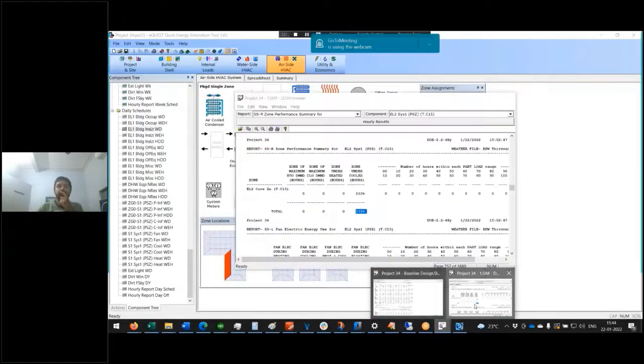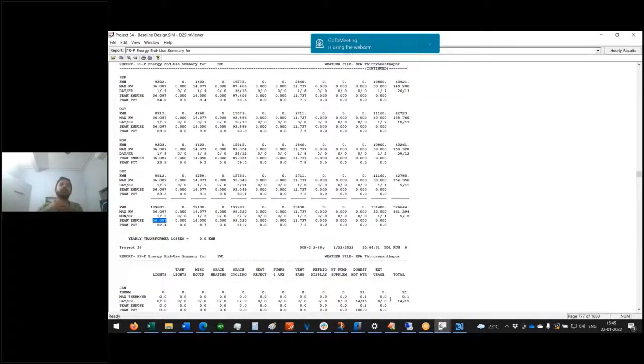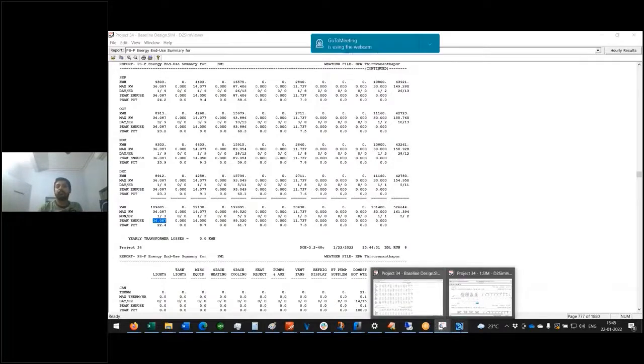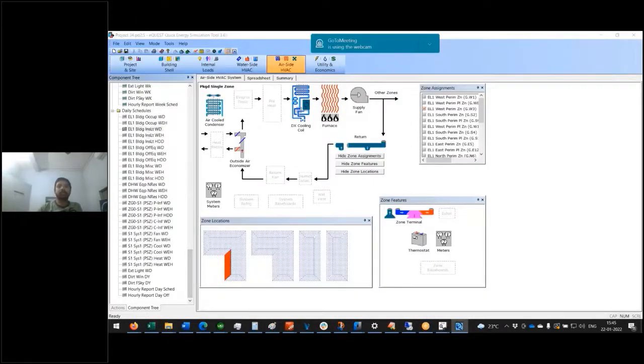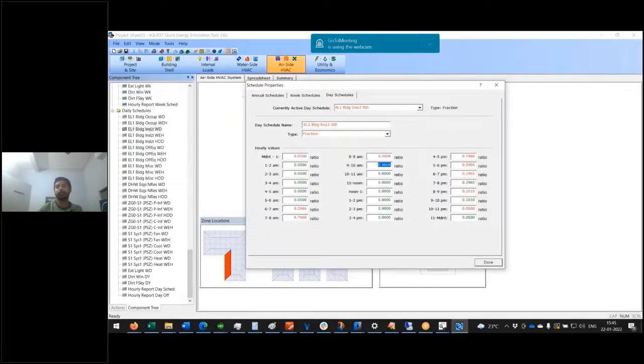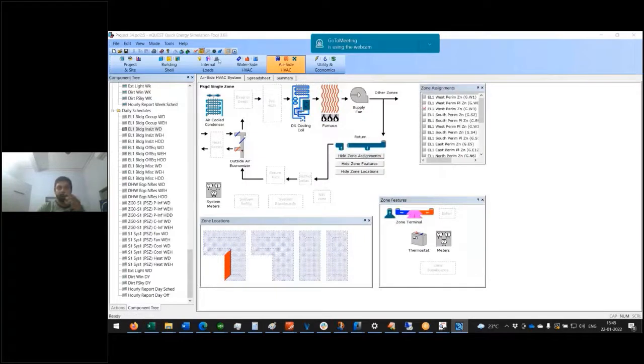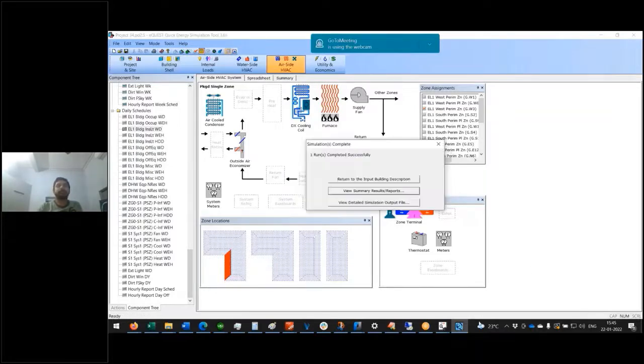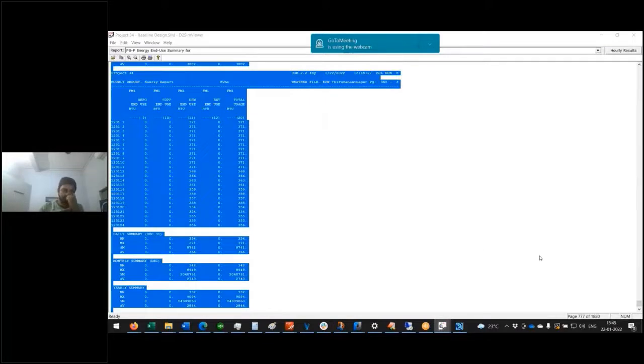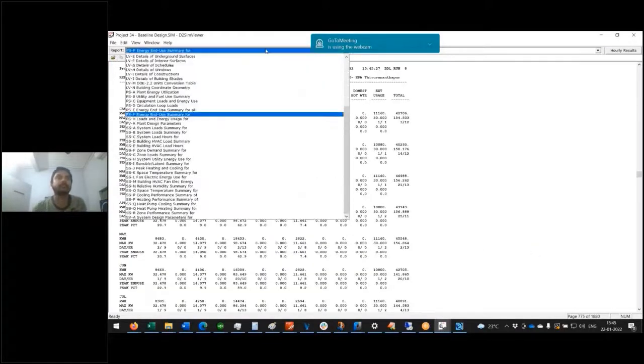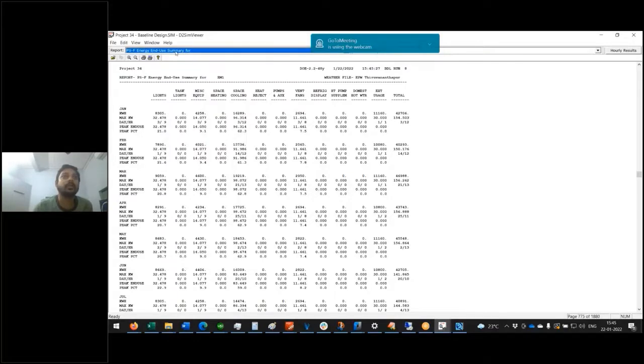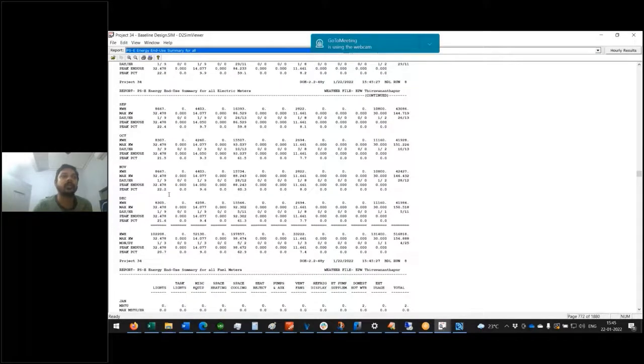Ideally, whatever you have on the lighting drawings, when you sum up all the kilowatt, the total should sum up. This kilowatt should match, right? And of course, the schedule should remain the same. I'll change this to 0.9. If I simulate this, there you go. So that's that.